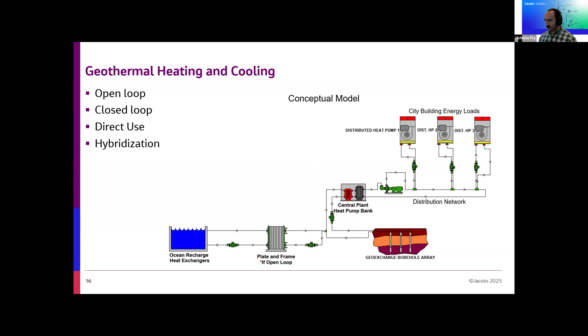You can think of operationalizing that in the shoulder seasons, preparing for winter. When you have that network in the ground, one benefit is reducing the size of your bore field or geo-exchange system—instead of hybridizing through auxiliary equipment like dry coolers or supplemental heat sources, you can rely on heat recovery across the network itself, since buildings demand heating and cooling at different points in time.